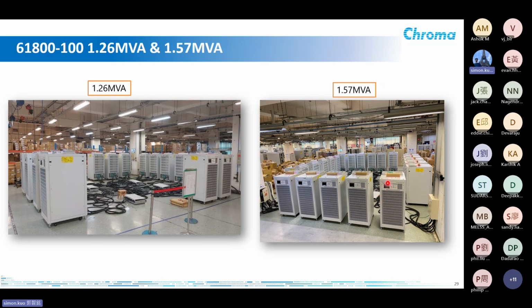Some of them are acting as source, some of them are acting as loads. We test each phase individually because we weren't able to set up a total testing setup — for example, for the 1.5 mega we'd need 30 pieces of the 618-100 to do a total test, but we aren't able to get that quantity of machines, or we'd need a lot of space to do so. So we test each phase individually.